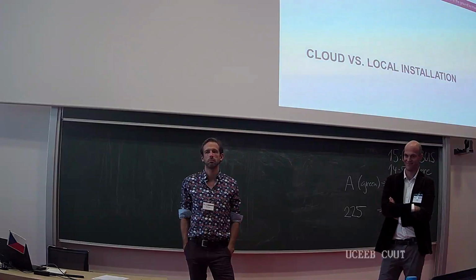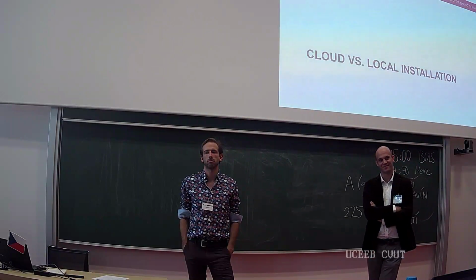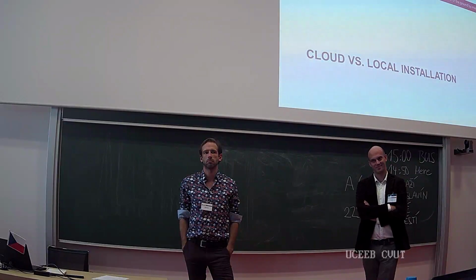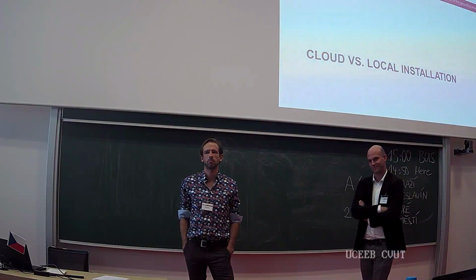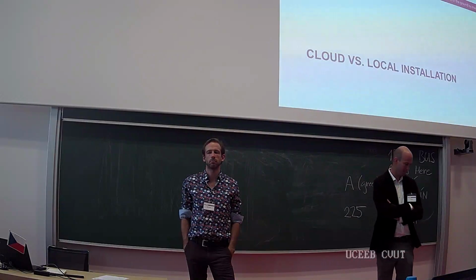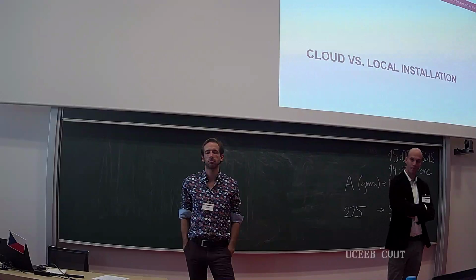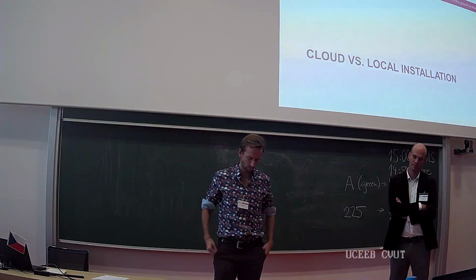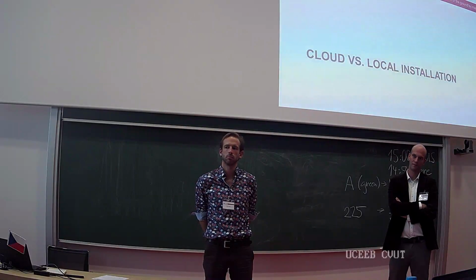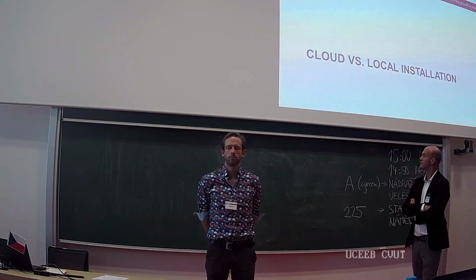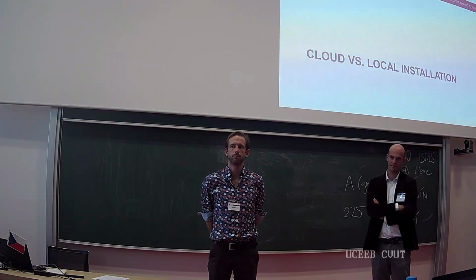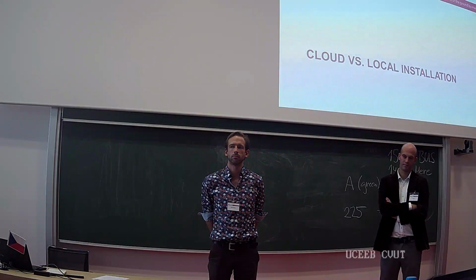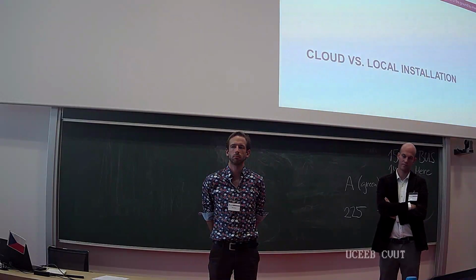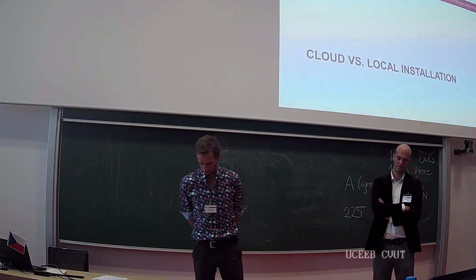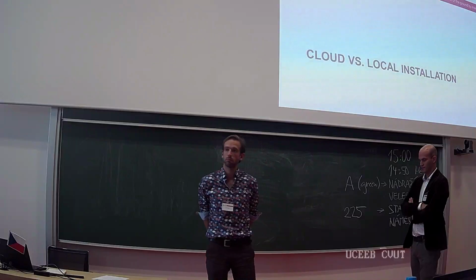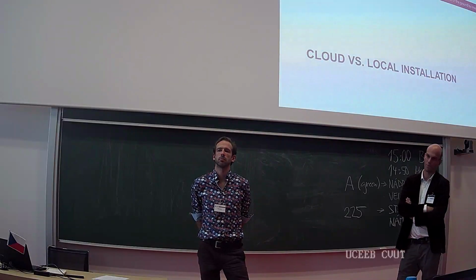Finally, in this project we are speaking about hybrid systems, and as Wim said, to have a cost-optimal system, you need to use it a lot for both heating and cooling. If you have a heat pump running for 1,000 to 2,000 full load hours for both heating and cooling, you can pay it off really quickly, even less than 5 years. If you design your system so the heat pump covers both cooling and heating load, and the additional heating load is covered by a secondary system like a gas boiler, you get your money back pretty fast.